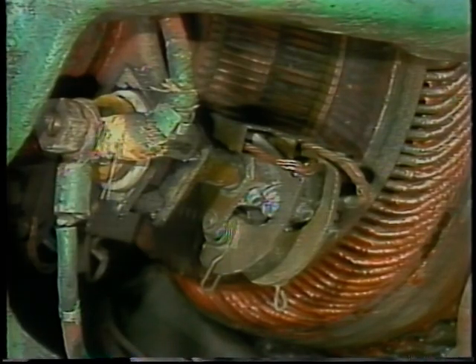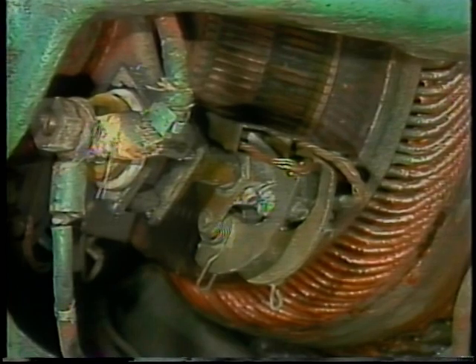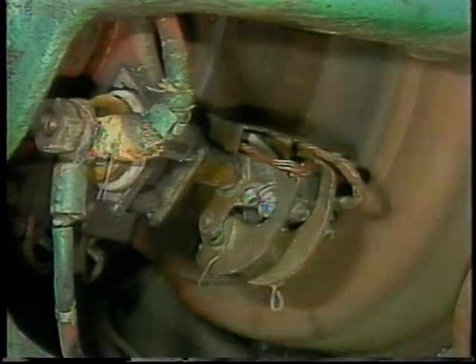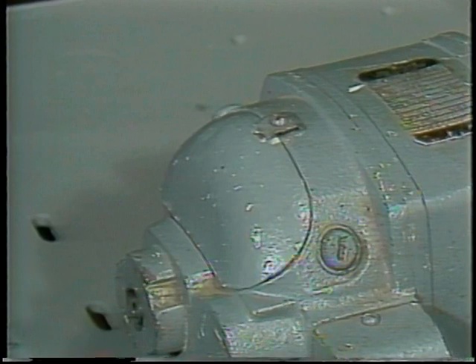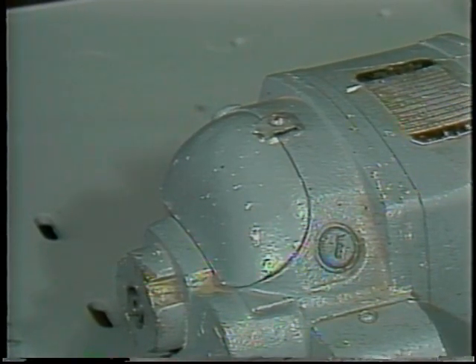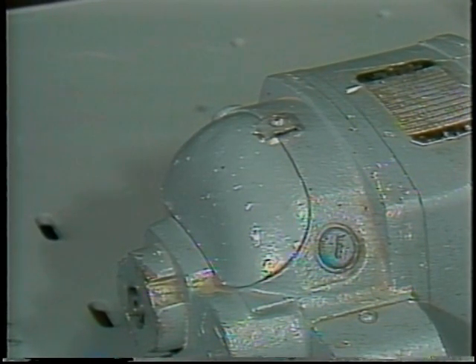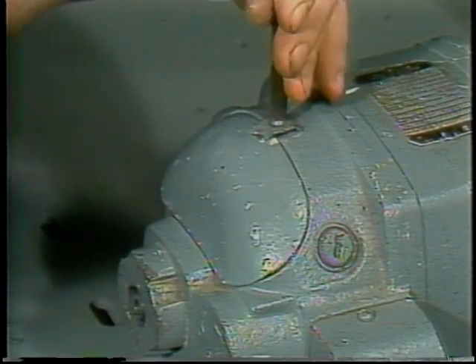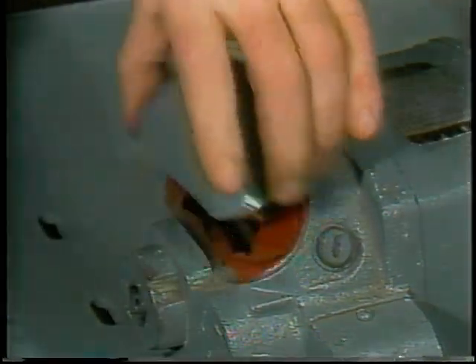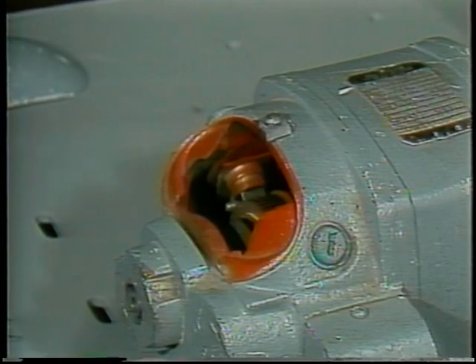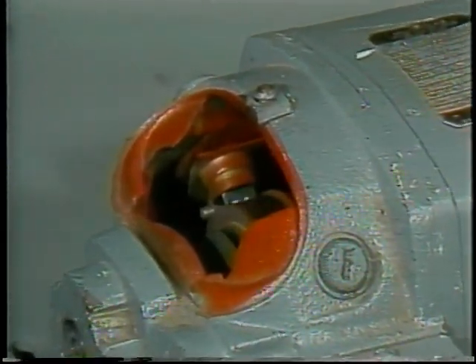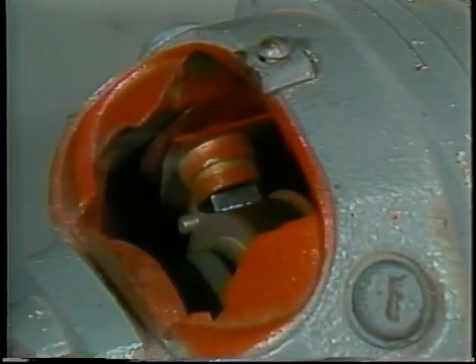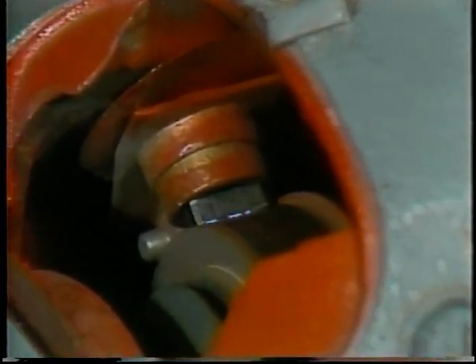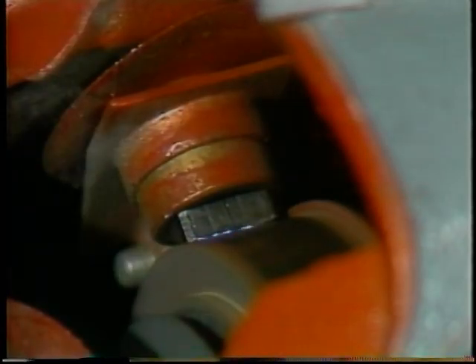Finally, routine maintenance includes servicing the brushes and commutator in DC motors and some AC motors. In most motors, you can see the brush commutator contact if you remove an inspection or access plate. Check for sparking when the motor is running under load. Shade the light if necessary. Slight sparking is okay in some motors which run intermittently or under light load, but any sparking in a motor under heavy use means that internal damage is being done.